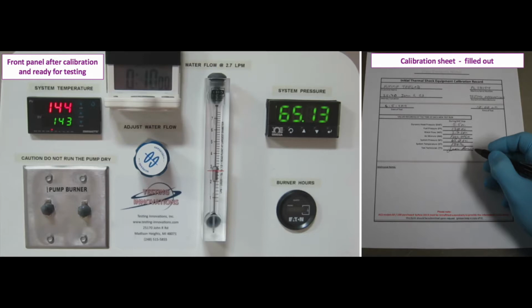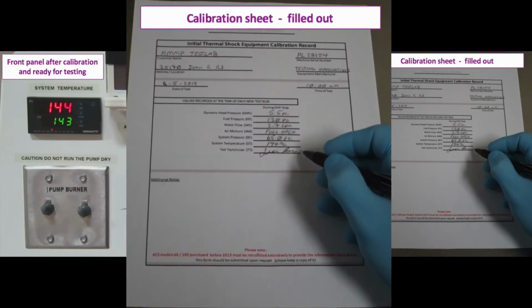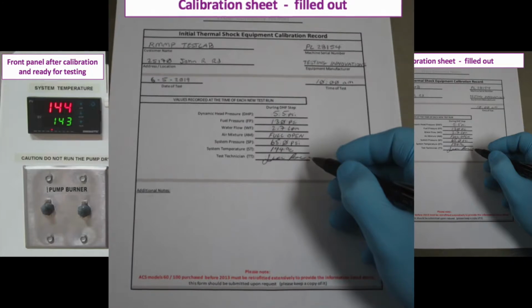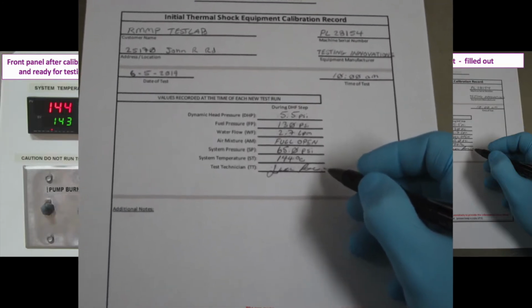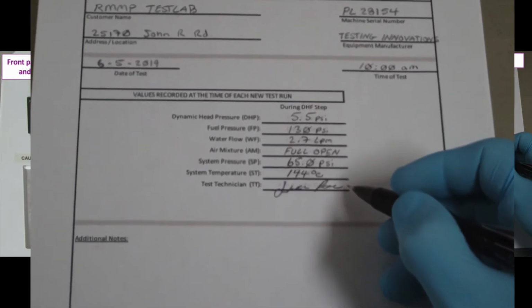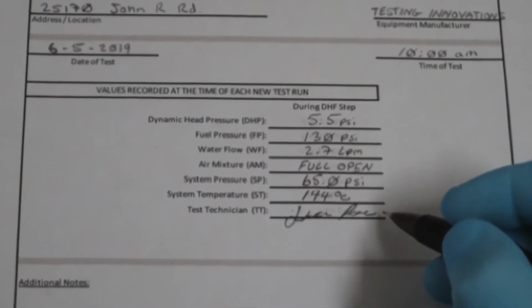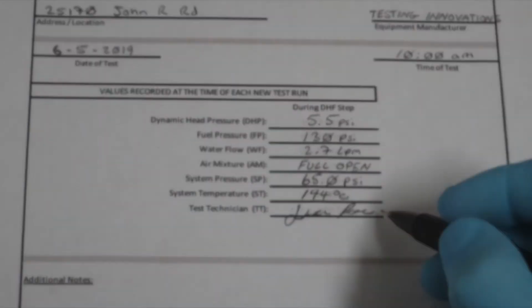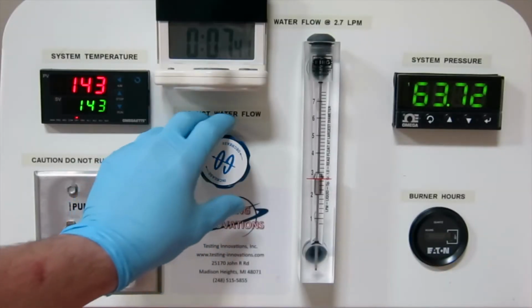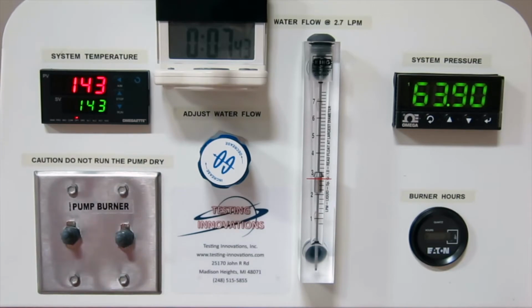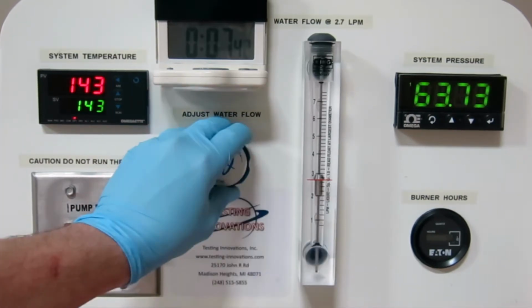So let's recap. On your screen you can see the system pressure, system temperature, and water flow rates that have been recorded during the calibration procedure on this particular day. These values have now become target values that need to be maintained during actual sample testing. This ensures that you will be running a valid test with 5.5 psi of dynamic head pressure at the required 2.7 liters per minute. This next section will help you understand what a normal testing session with this thermal shock equipment will be like.